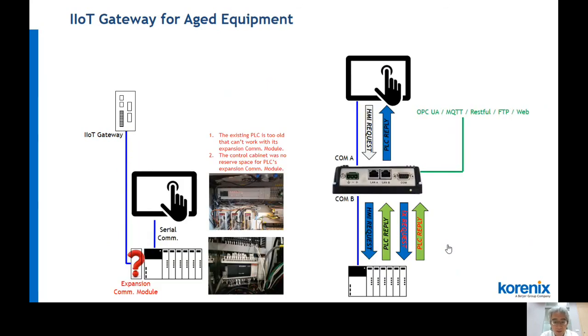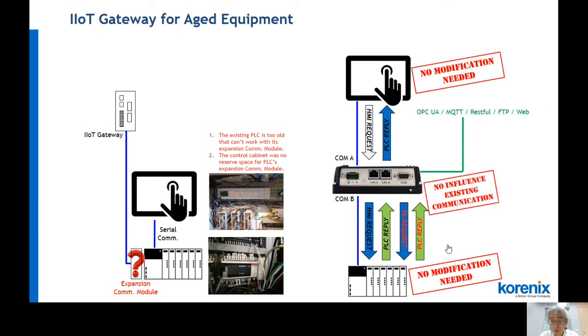Some cases are very interesting, just like when the controller, the PLC, and the equipment HMI already occupy all of the communication interfaces, so you don't have any communication port to get the data. Our gateway has some special functions called transparent mode. We can add our gateway in the middle, between the existing HMI and the controller, wired transparently, so the HMI and PLC can do their work as usual. And we create another new communication port to read the data from the PLC. So we don't have to replace the existing PLC or HMI, and we have no interference with the existing communication, while still getting the data for digitalization. So this is another solution for aged equipment.